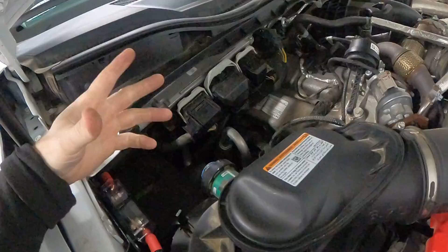It comes over here to what's called an ANL fuse block. ANL is the type of fuse, a very large fuse. You size a fuse for the wire size. This is 1/0 cable here, capable of carrying about 250 amps, so you have I think a 200 or 250 amp fuse. I don't remember exactly what I put in there.